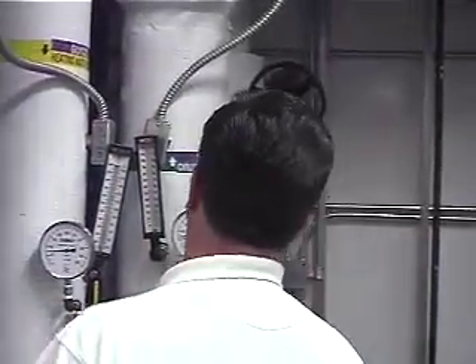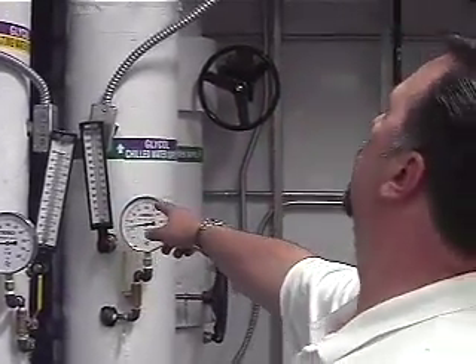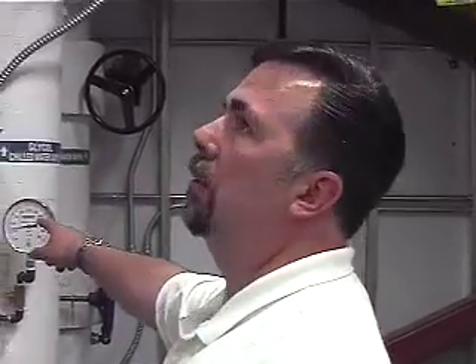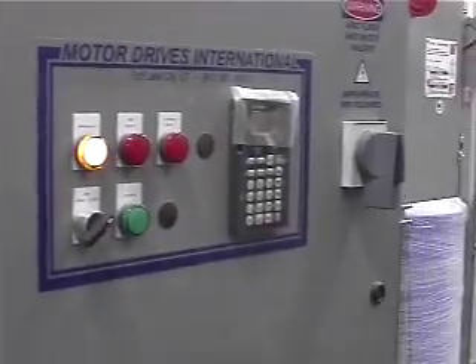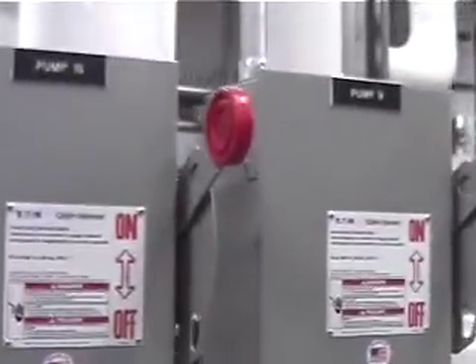This heat exchanger is heat exchanger 1, the chilled water coil heat exchanger there. This is the one where we modulate the speed of the pump. It doesn't have a valve on it. So if you look here, you've got your VFD right here. This is your VFD for pump 3, which will modulate to maintain the chilled water temperature so you can maintain your discharge air. Pump 4. Then you've got your disconnects for pump 5 right here.